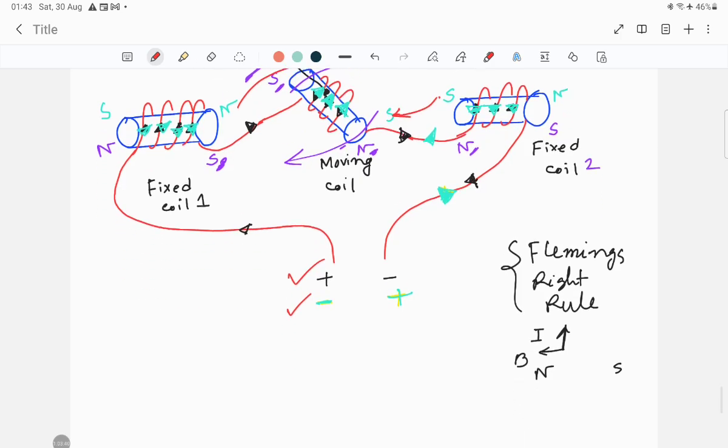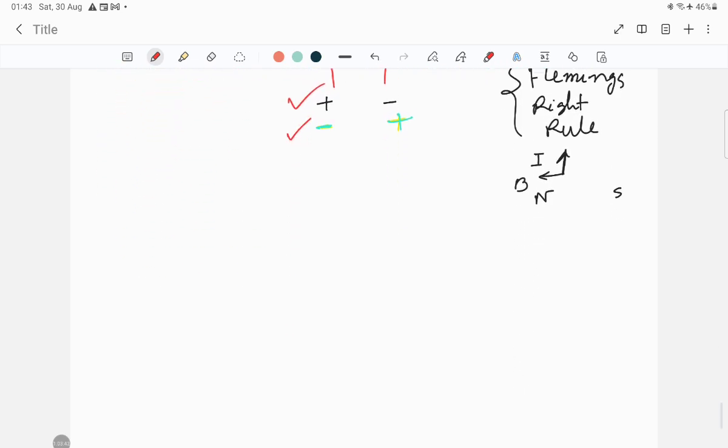Okay, now there are some certain things that you need to know, because again there is the same arrangement like the PMMC and the electrodynamic meter. They have the same sorts of arrangement, because whenever a deflection is being produced, you have to again make the pointer return to its initial position, so you have to provide the hair springs as well in the electrodynamic meter.